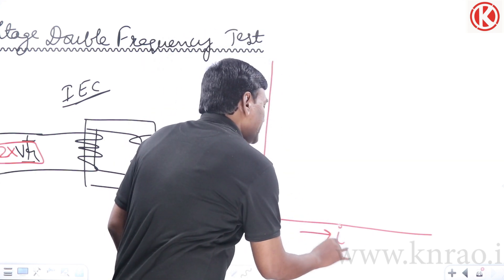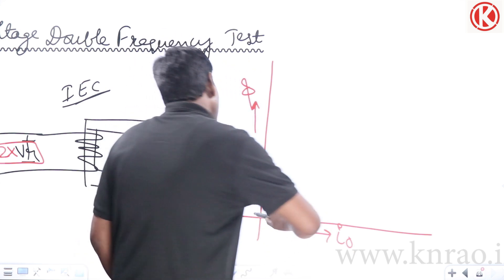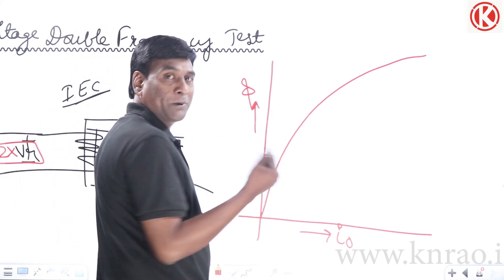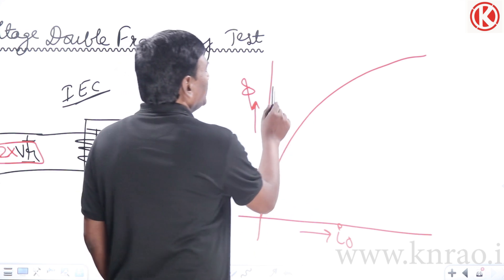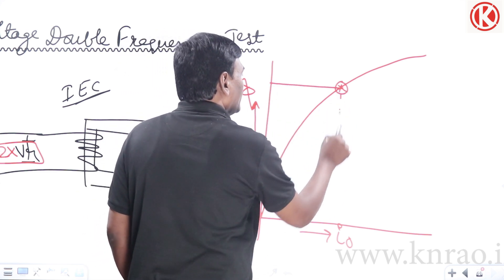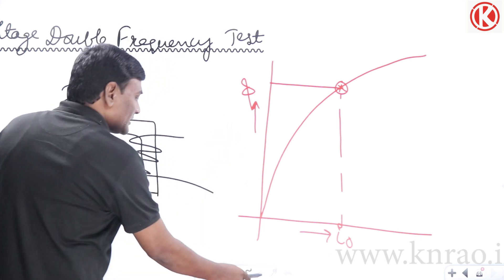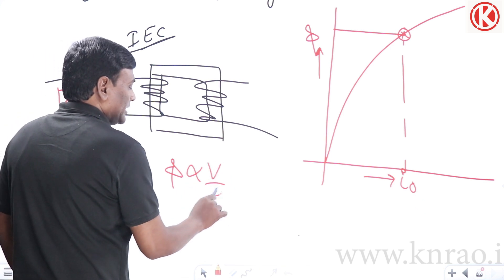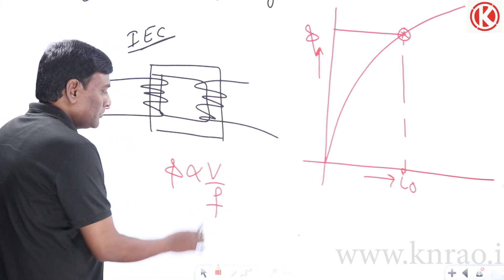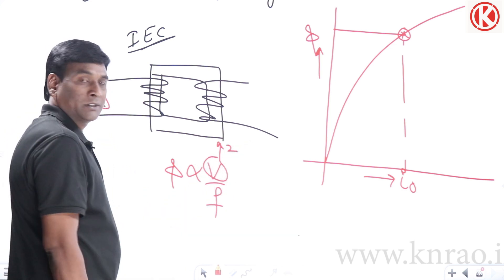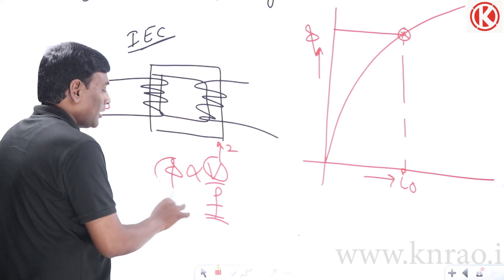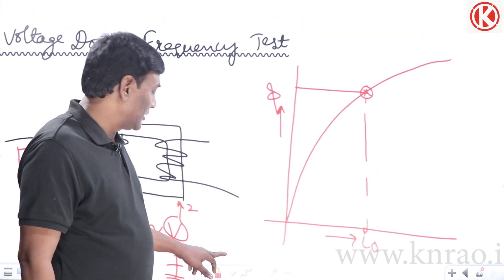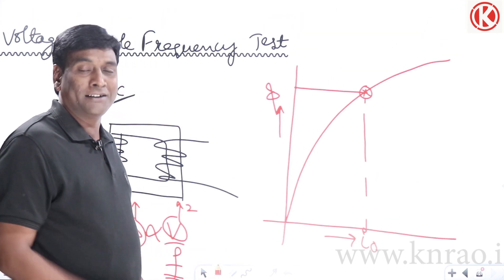We already know the magnetization characteristic — the B-H curve. The no-load current versus flux characteristic is non-linear, and the operating point B-max should be in the non-linear region. This operating flux is decided by the V/f ratio — voltage divided by frequency. So if you increase voltage by two times while maintaining the same rated frequency, the operating flux is going to be doubled.